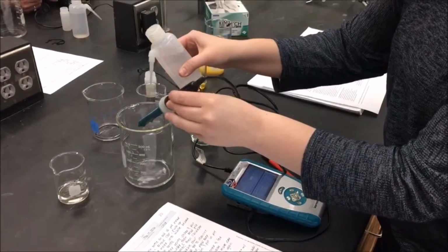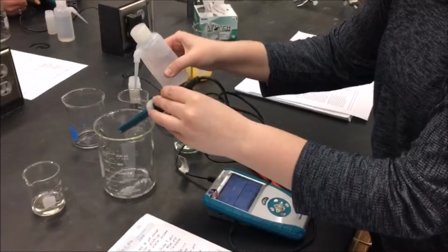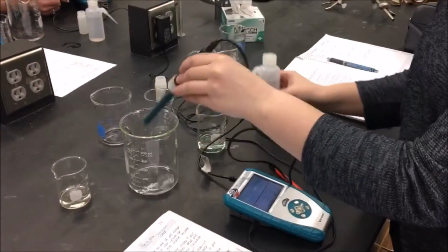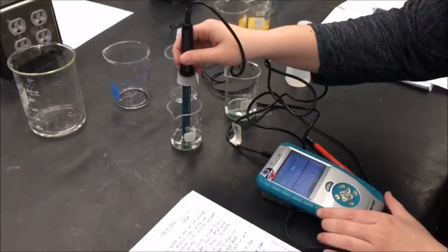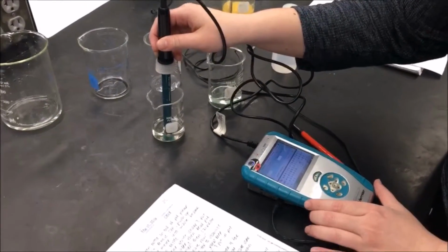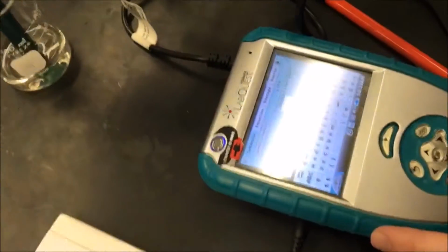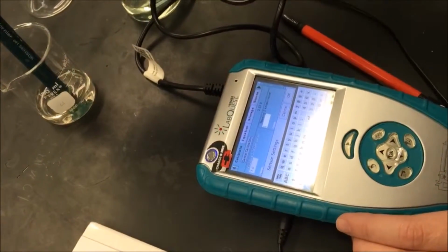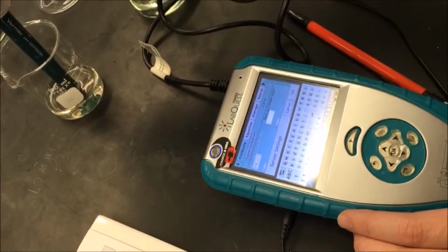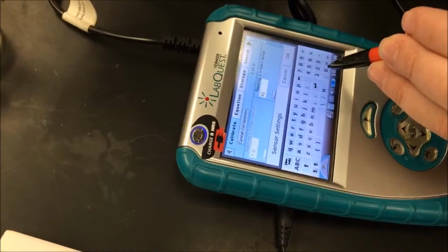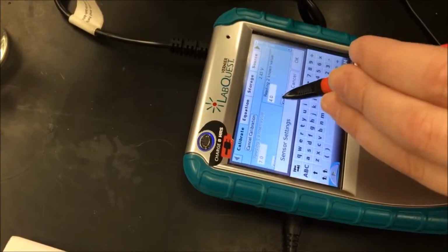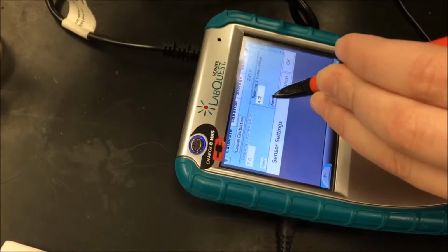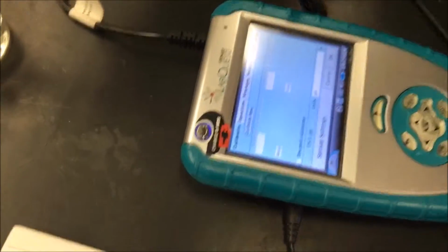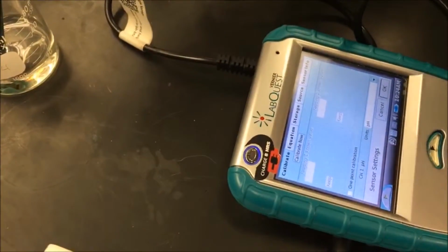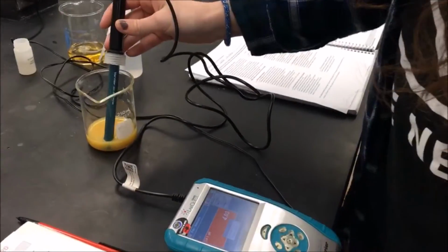When not actively using the probe, remember to leave it sit in the beaker with water. Never leave it alone on the lab bench. This is because the probe is very sensitive and mishandling can lead to faulty readings, so be careful to handle the probe correctly. When calibrated correctly and handled properly, the pH meter should come out with a pH value for your unknown substance. This value should be accurate and will help determine if your acid is strong or weak, or if it is a base that is strong or weak.